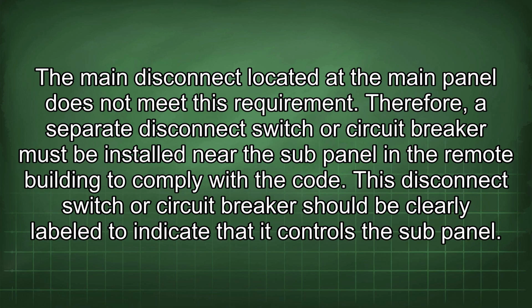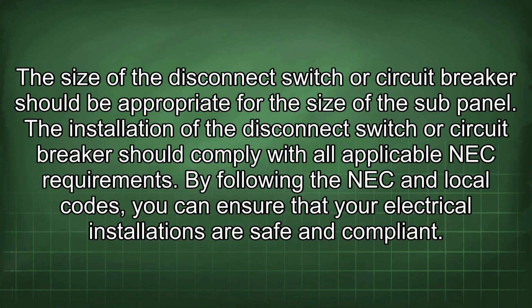Therefore, a separate disconnect switch or circuit breaker must be installed near the sub-panel in the remote building to comply with the code. This disconnect switch or circuit breaker should be clearly labeled to indicate that it controls the sub-panel. The size of the disconnect switch or circuit breaker should be appropriate for the size of the sub-panel. The installation of the disconnect switch or circuit breaker should comply with all applicable NEC requirements.